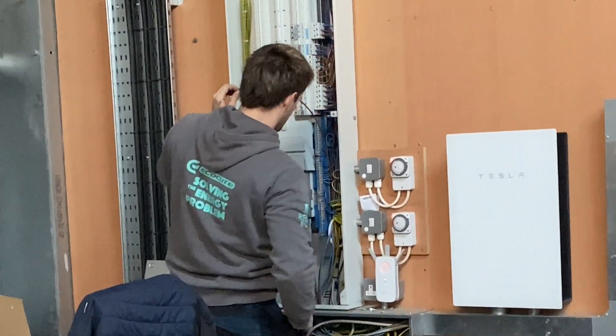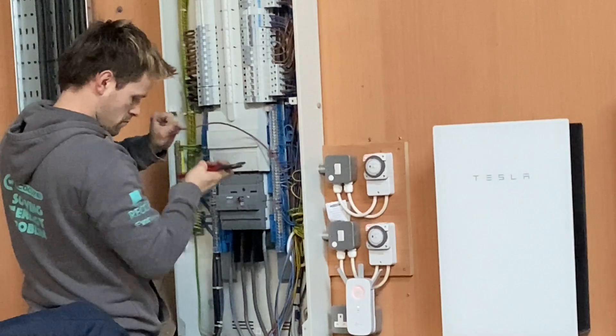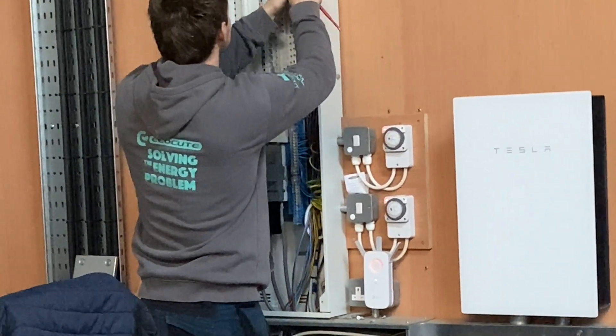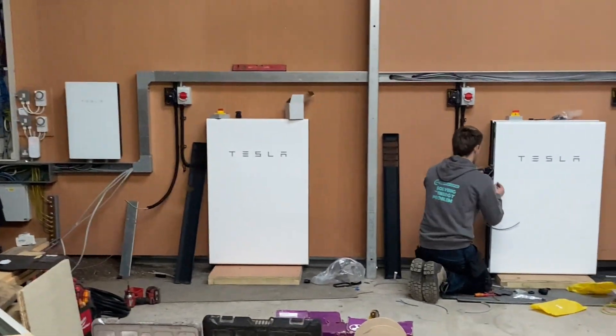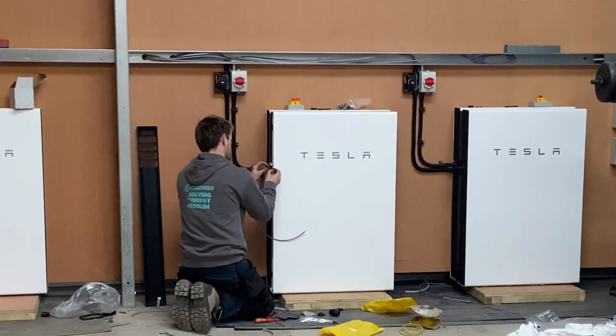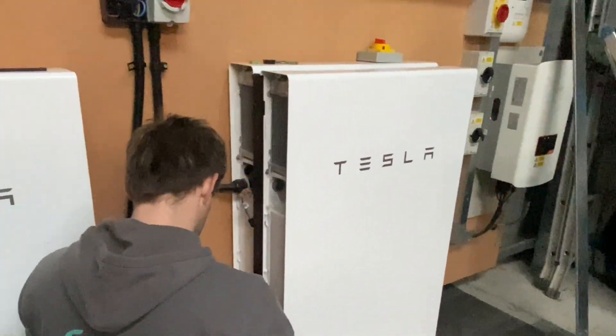Now that we've got the Powerwalls out of the van and in position, let's crack on. Corey is here terminating the new circuits that we've run from each new Powerwall. We've gone behind the false wall back to the mains board. You might ask why we've not gone into the gateway — quite simply on this one, the gateway is full. So we've gone back to the main board. You can see him now just finishing off the cable glands and terminating on the Powerwall side.